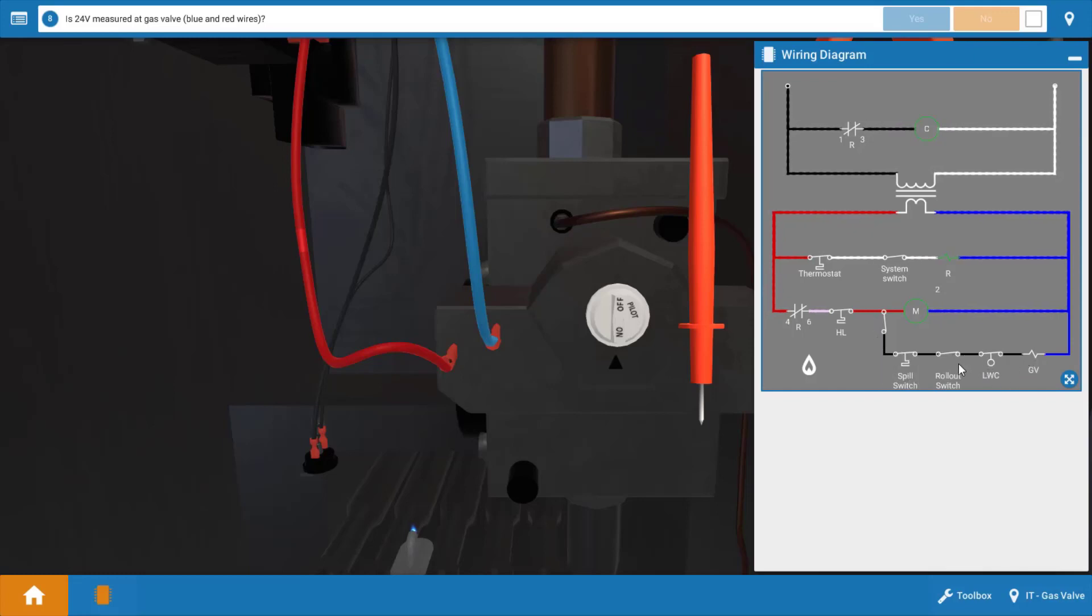Low water cutoff, rollout switch, spill switch, and of course the vent damper end switch. Now we knew the motor of the vent damper is working fine, but we don't know that the spill switch closed.